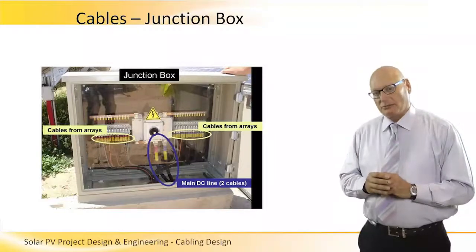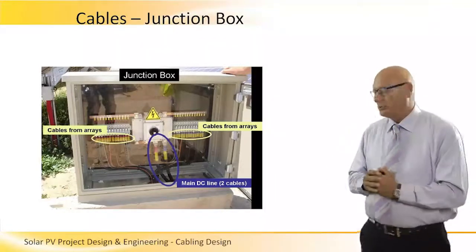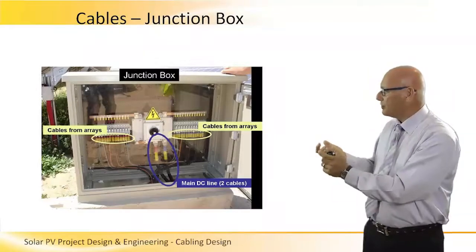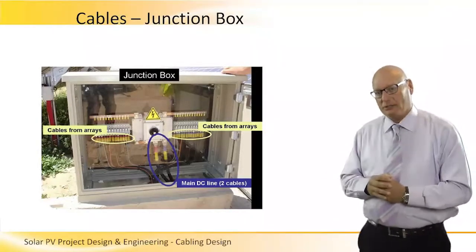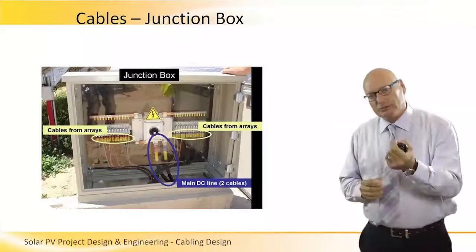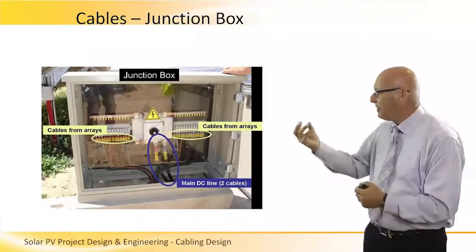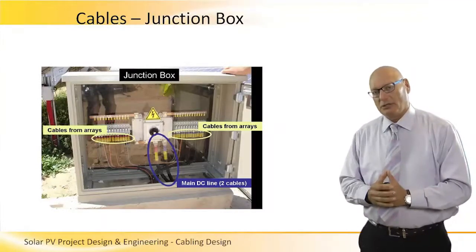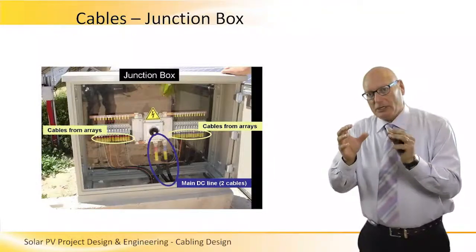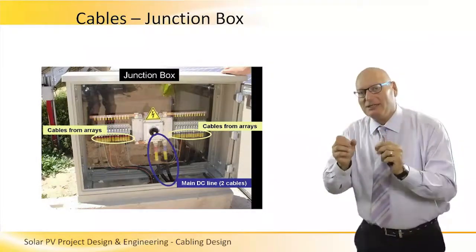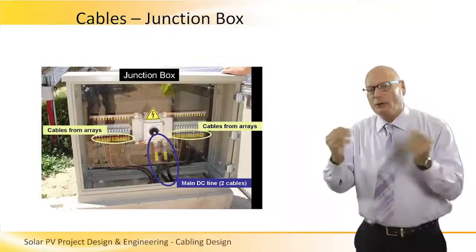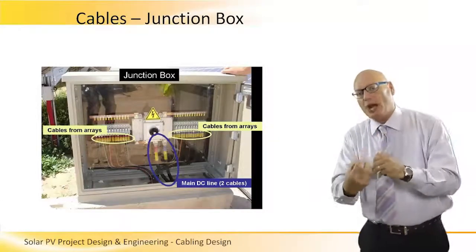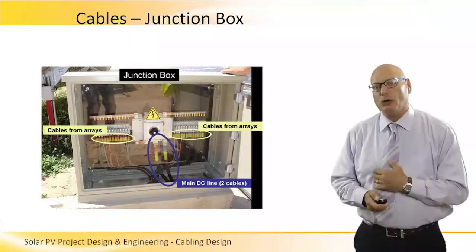Here is a good example of a junction box — and remember, we're still looking at the cables. On two sides of the junction box we see the cables from the arrays. The diameter of those cables is relatively smaller than the main DC line — two cables, plus and minus — coming out of the junction box. Please consider the difference in the diameters of the input cables coming from the array versus the output cables, plus and minus, coming out of the junction box. That's a very good example that one should follow.